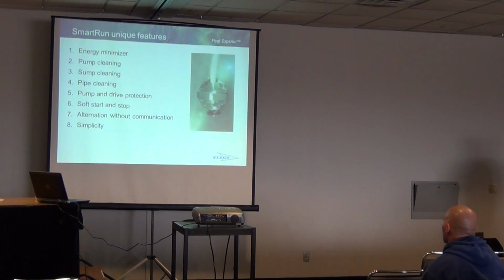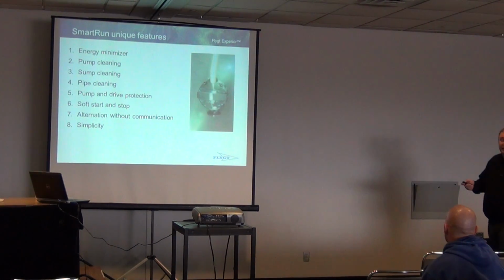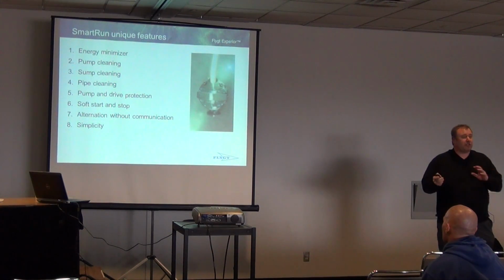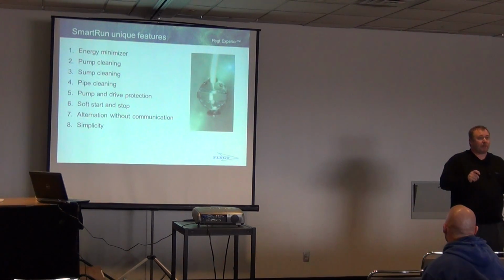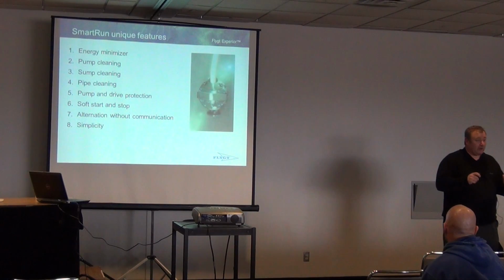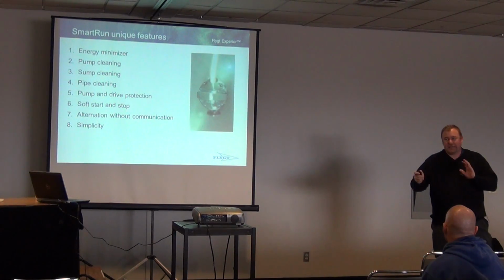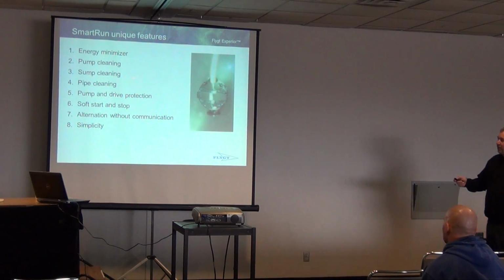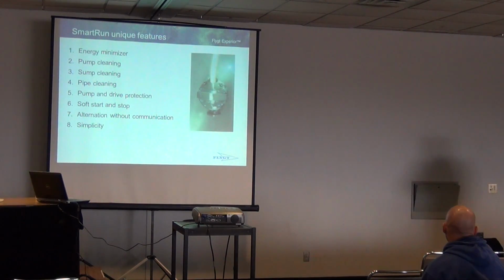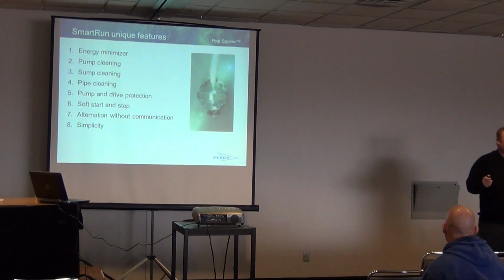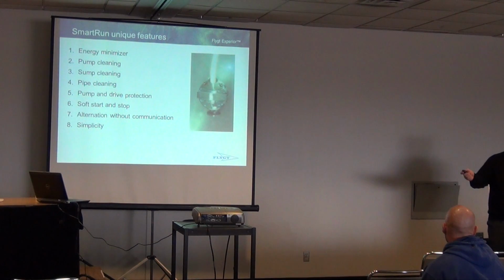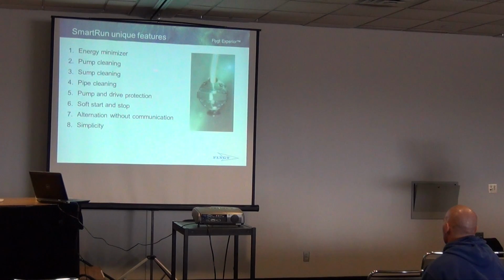Pump cleaning functionality. What does that really mean? It means that if it's sensed that that pump is going to clog at all, it will literally take that pump, and all of this functionality, operators can decide if they want it or they don't as well. So it's completely programmable, but it has pump cleaning functionality where it'll take that pump, if it's starting to send an amperage change from a clog, we'll literally stop that pump, run it in reverse for less than 1 second, clear the clog, and start rotating in the right direction again. It has that built right into it.